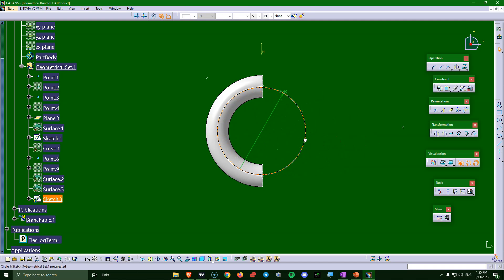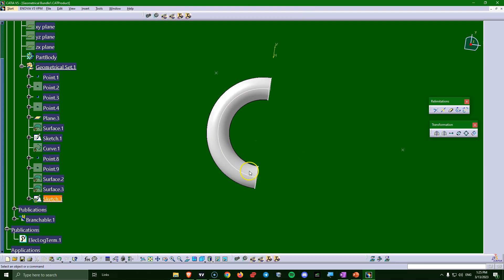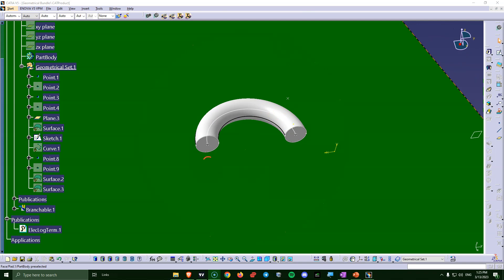I'll position the tangent circle by hand — you can see it's 40 mm in diameter, just tangent to the curvature of the cable. This proves it visually. So if you have two fixings where you need to route the cable, you need to calculate the distance between the two retainers from their central axes. The distance between them must be at minimum the diameter of the circle tangent to the bending radius — and I'd recommend adding at least 20% extra to that distance.